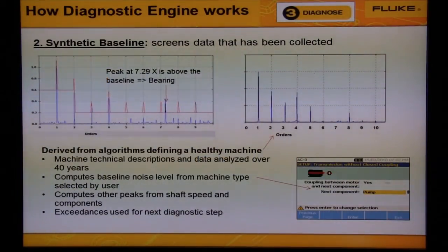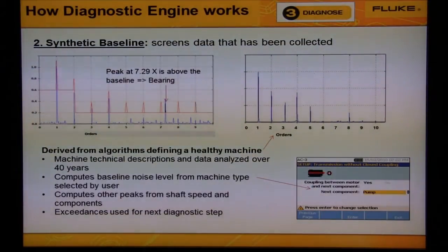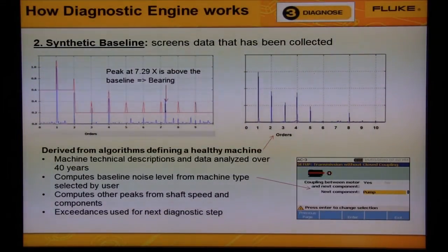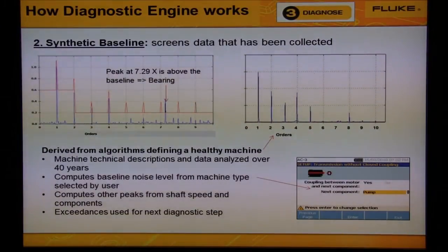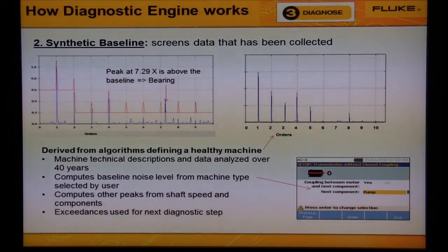Step number two is to generate a synthetic baseline. This is performed every time the measurement is diagnosed. From the information selected by the user during machine setup, the diagnostic engine searches its database — compiled over 40 years from hundreds of thousands of machines — to find what a machine of the same category would look like.